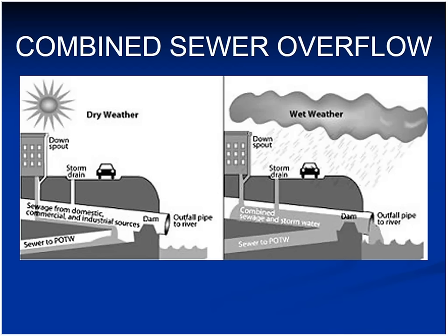You may have heard the term combined sewer overflow. This is a situation that's installed in a collection system in order to protect the plant during extremely high flows. We'll learn about these guys next week, but we're dealing with single-celled bacteria. 95% of the organisms in the wastewater treatment are single-celled bacteria, and if you just triple the flow through a plant, they can't swim upstream that well. If you don't protect your plant, you're liable to lose all of your bugs to the river. It's not a good thing.